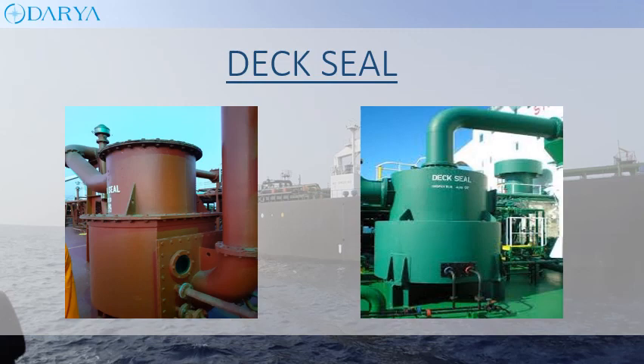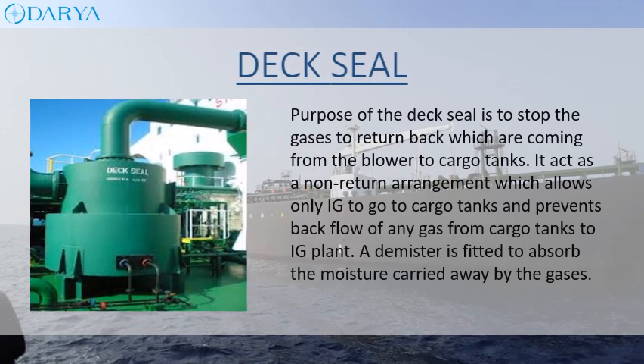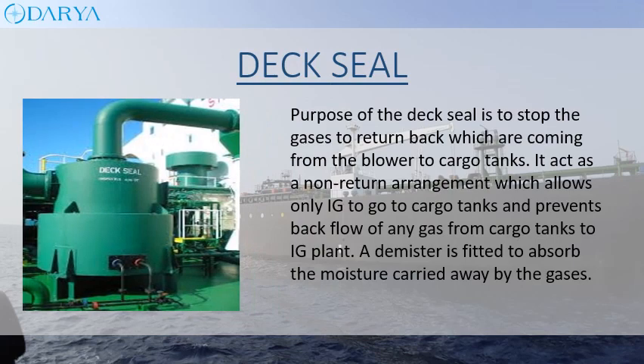The purpose of the deck seal is to stop gases from returning back from the blower to the cargo tanks. It acts as a non-return arrangement which allows only IG to go to cargo tanks and prevents backflow of any gas from the cargo tanks to the IG plant. A demister is fitted to absorb the moisture carried away by the gases.